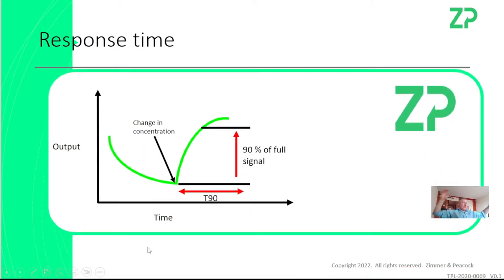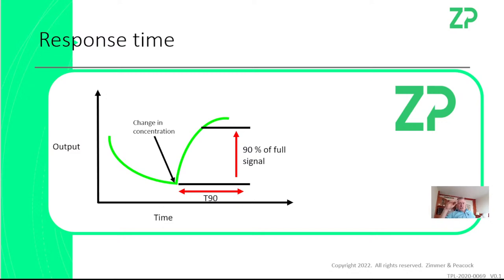Response time is really similar to settling time. I'm at baseline, I add an analyte at a known concentration, there's a rising signal, and it's just really the response time. Again, T90 is the time it takes to get within 90% of the signal — there's a final plateau which is the last 10%, but sometimes reaching plateau can take a really long time. You're really just interested in what it takes to get within 10% of the plateau — that's your T90 time.